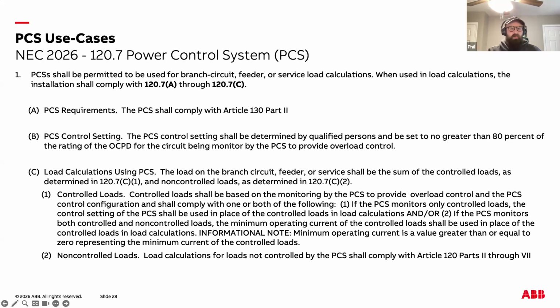The informational note is important here. It clarifies that the minimum operating current is simply a value greater than or equal to 0, representing the lowest current the controlled loads could draw. This prevents designers from assuming unrealistic or artificially low values. All non-controlled loads continue to be calculated using the traditional methods found in Article 120, Parts 2 through 7. This section of the code is especially relevant today as more installations include EV chargers, heat pumps, and other large loads that benefit from PCS-based load management.